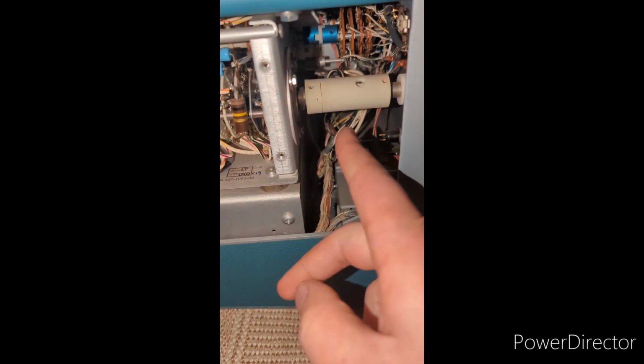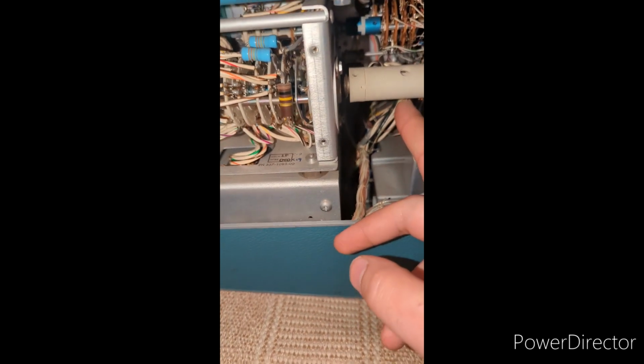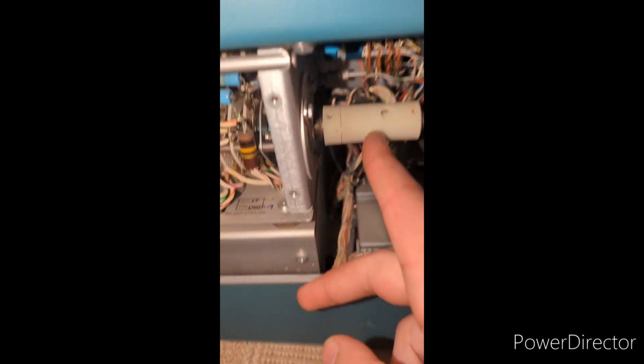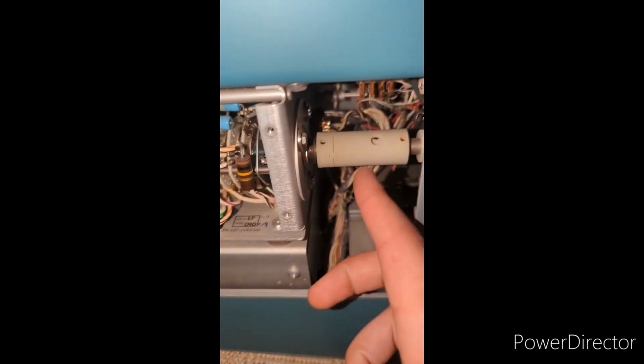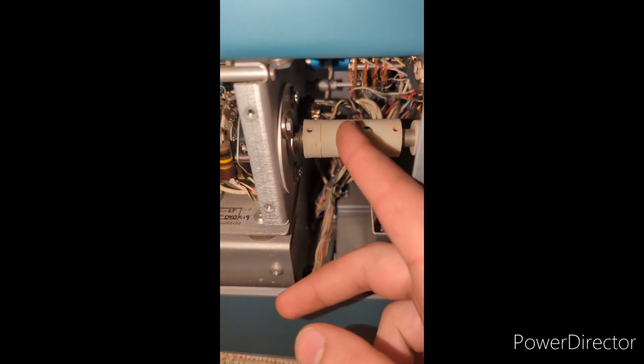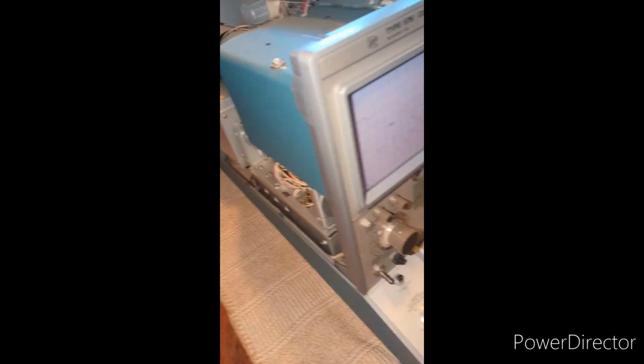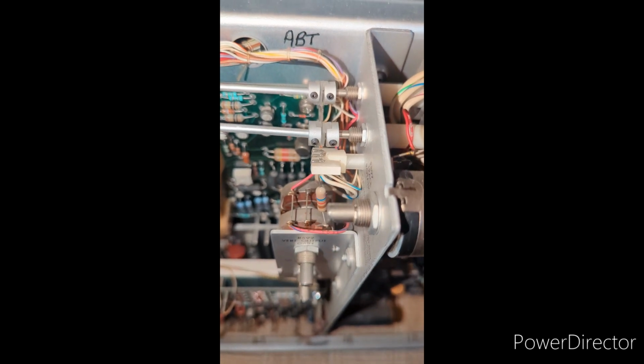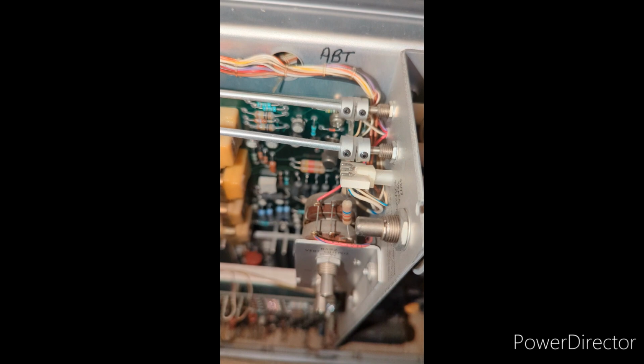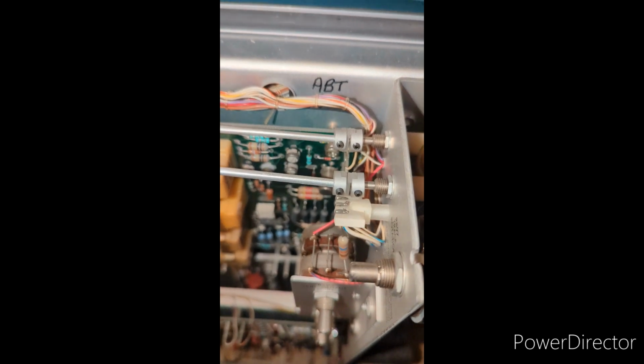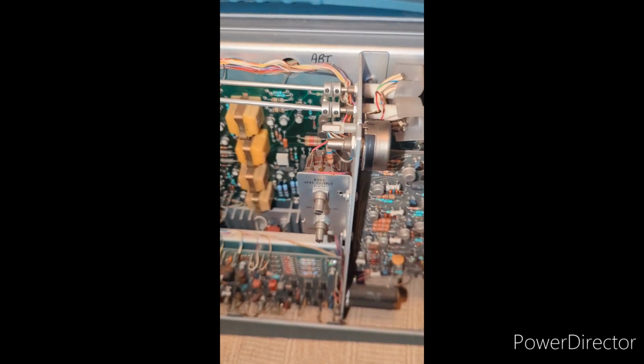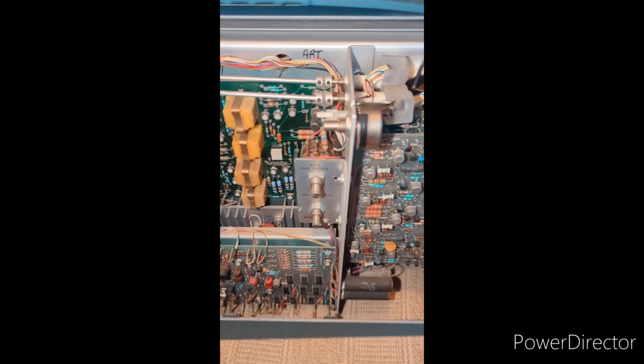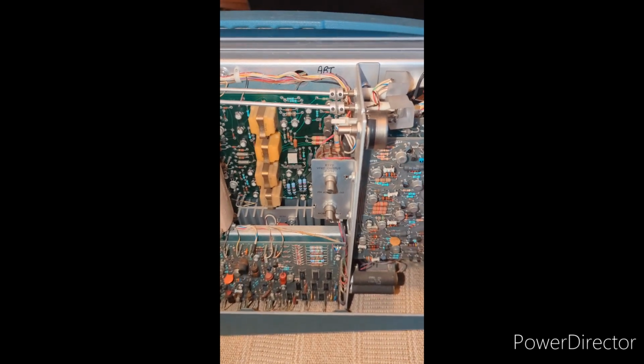So a lot of these switches or pots, knobs, will run the length of the instrument, and they are usually connected to the actual switch via these couplers. I've seen these break. Someone who's selling one of these who may not be familiar with them will think the whole instrument is non-functional, and it could just be due to one of these quick couplers being bad. Doesn't look like that is the case with this one. You can see all of the quick couplers are in place, which is good. And that's a relatively easy fix anyway. You can get these types of couplers in different sizes from Grainger or McMaster-Carr. So that would have been a relatively easy fix.